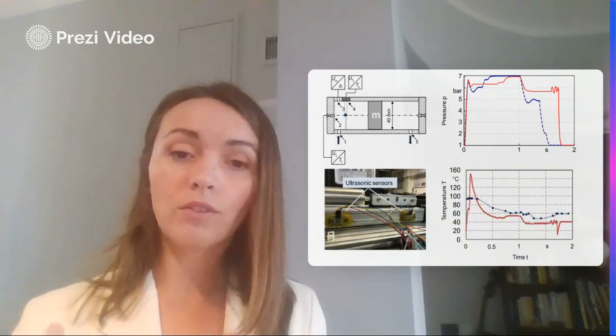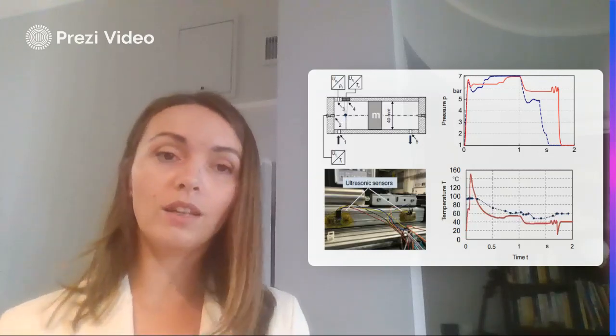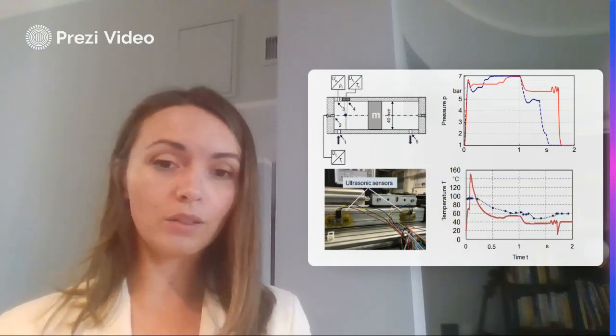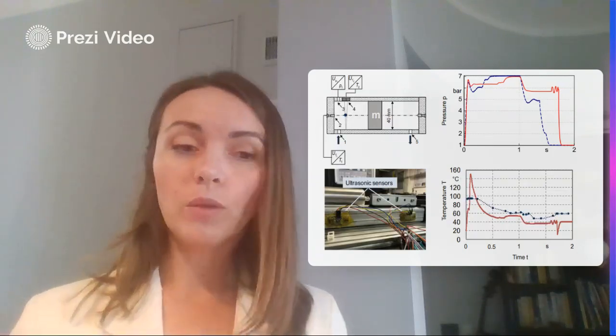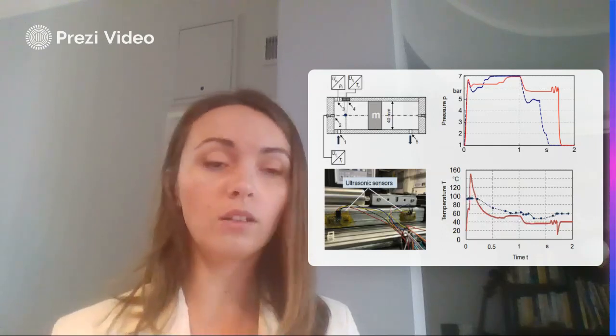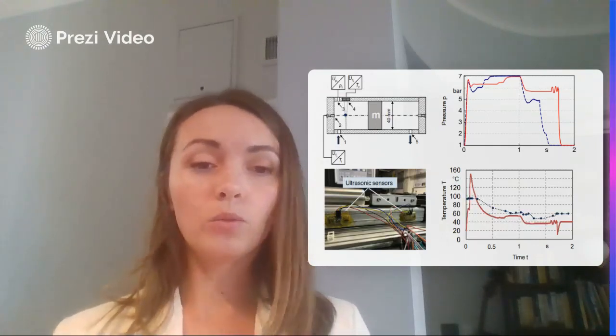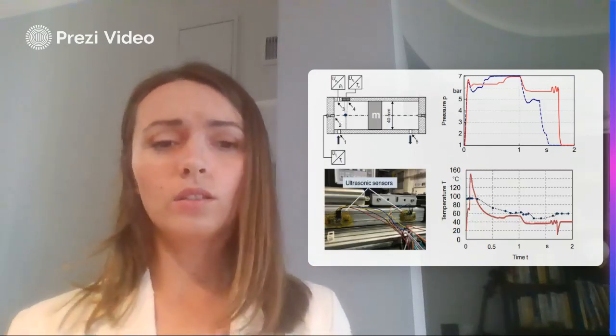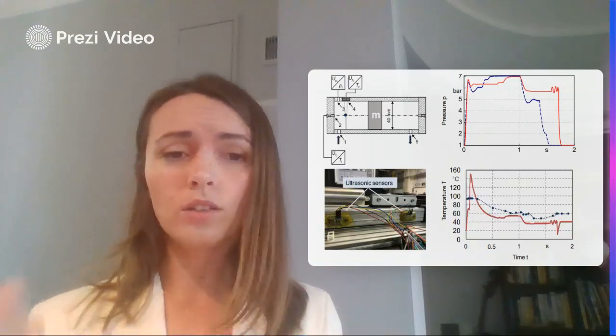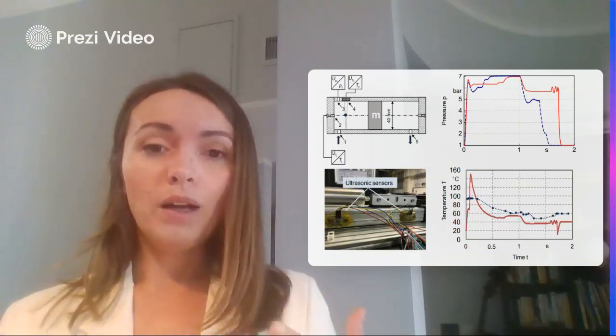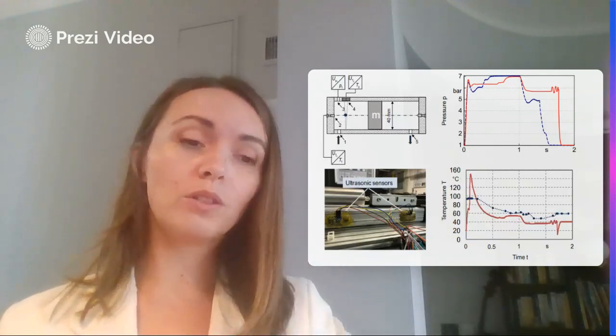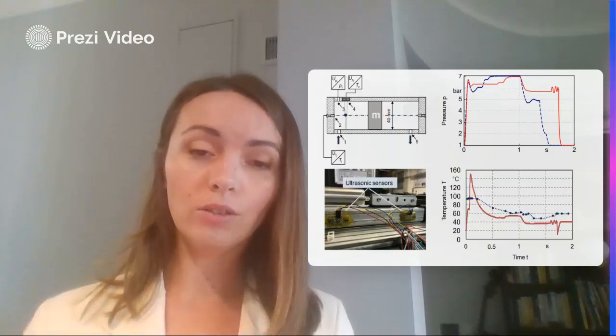There is also the problem of temperature measurement: the sensors are very inertial. It is very hard to get the temperature of the gas because the sensors measure their own surface — they heat up and measure themselves. This is why it is sometimes almost impossible to get accurate temperature measurements with traditional methods. An alternative method was developed in the lab, where you can also see the compression inside the cylinder. The blue line shows the measurement: compressed air goes up to 90 degrees and then cools down. It is not an isothermal process — it is closer to adiabatic and polytropic. The same thing happens in the compressor: temperature rises, and then we cool it down with intercooler stages.